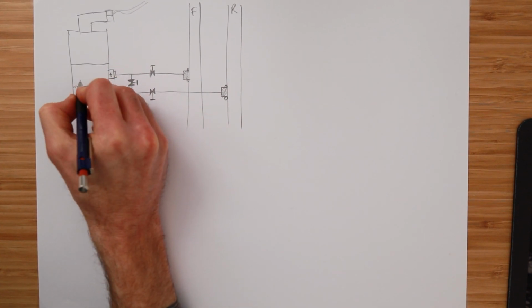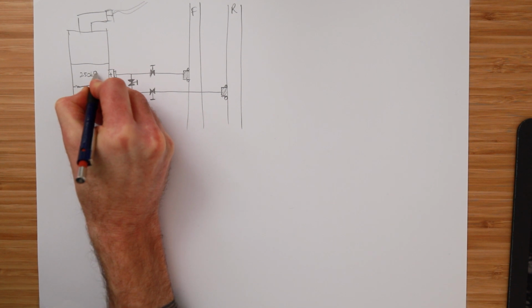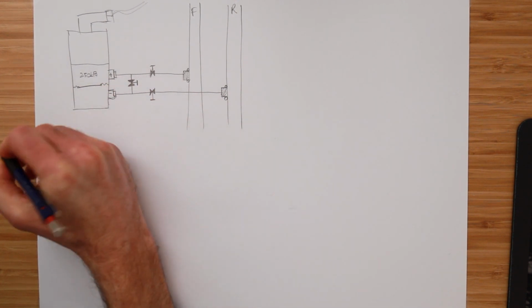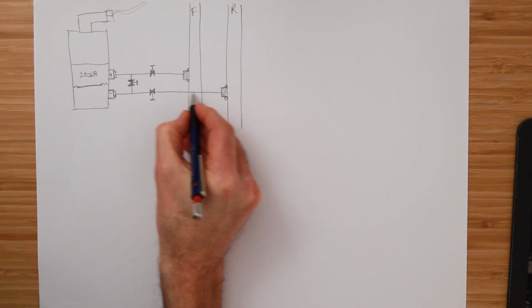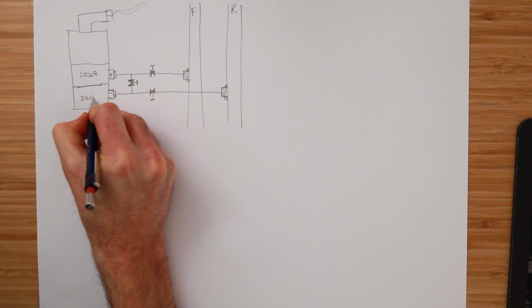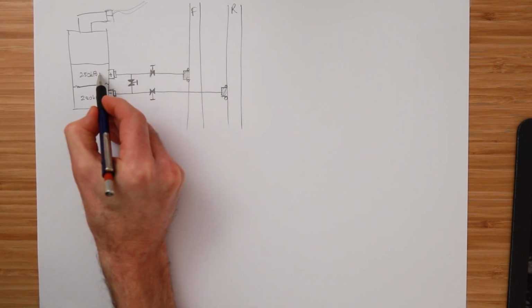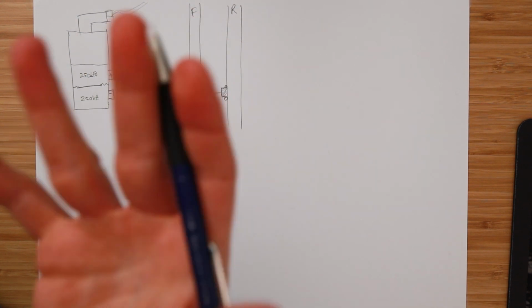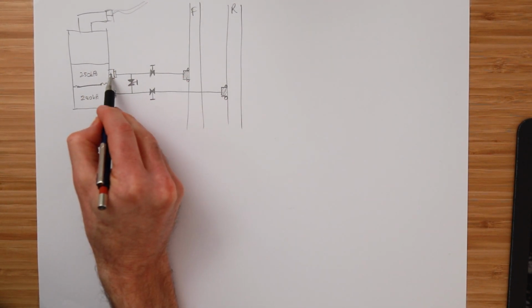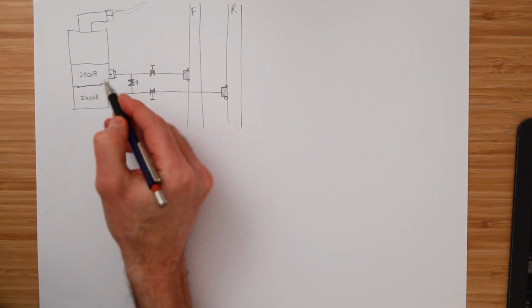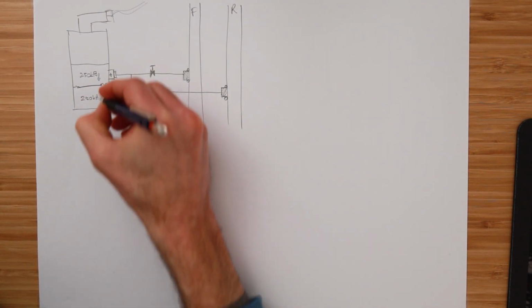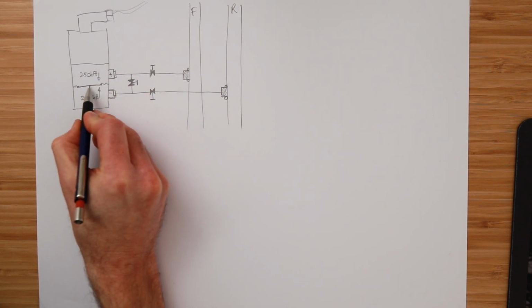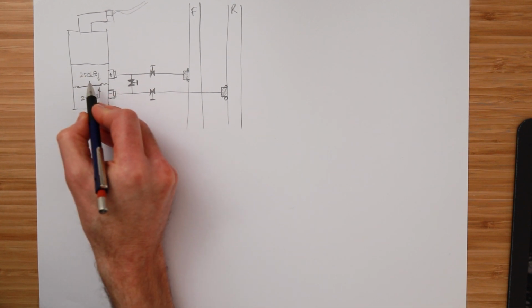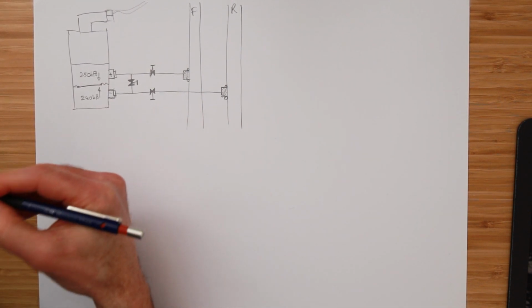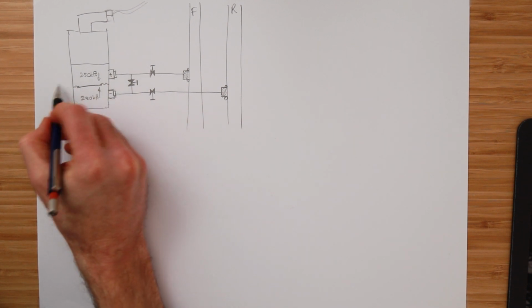So say for example, you've got 250 kPa of pressure sitting in here. And then when the system is completely turned off and there's no pumps running, there might be another 250 kPa sitting here. So there's 250 kPa here, there's 250 kPa here. This is the static head in the 30, 40, 50 story commercial office sitting on here. So because on the plus there's 250 and on the minus there's 250, there's 250 pushing this way and 250 pushing this way. The diaphragm is sitting balanced, and the difference, it's called a differential pressure transmitter because it's the difference between the plus and the minus, is 0 kPa.